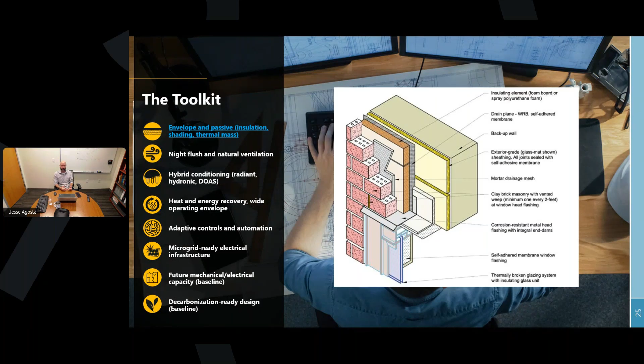Which brings us nicely to our next topic: night flush and natural ventilation. With a night flush strategy, at night you open windows and pull cool outside air through the building, relieving the hot air at the top. Throughout this process, the warm thermal mass of the building releases its heat and cools down inside. So if you have a really high thermal mass building, it can take a long time for the sun to warm it up the next day to the point of discomfort. Couple this with natural ventilation strategies, and we maximize the amount of time we can use outside air to cool the building as a whole.